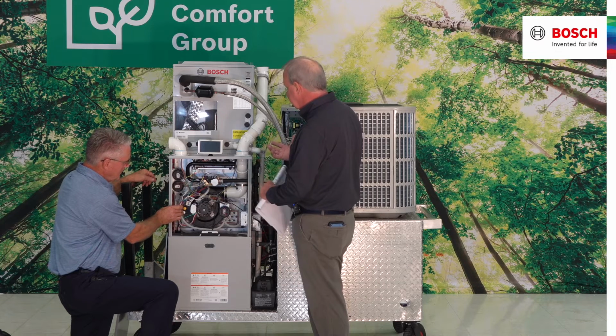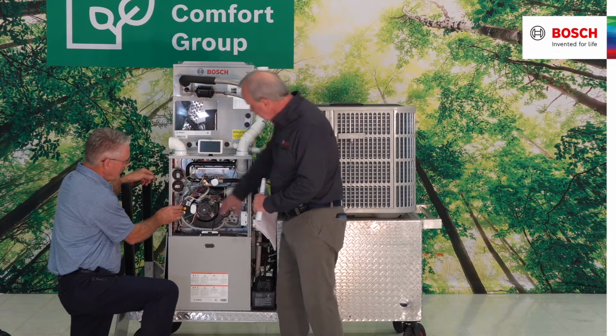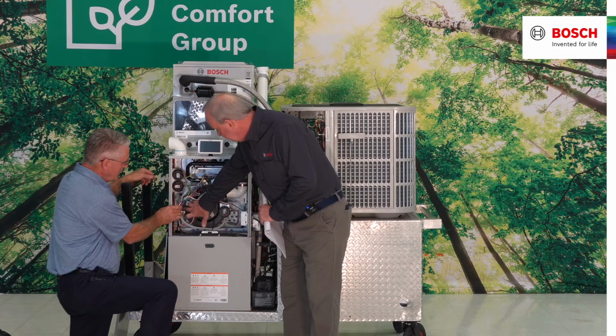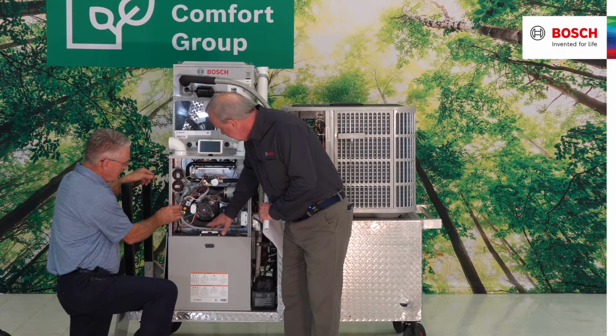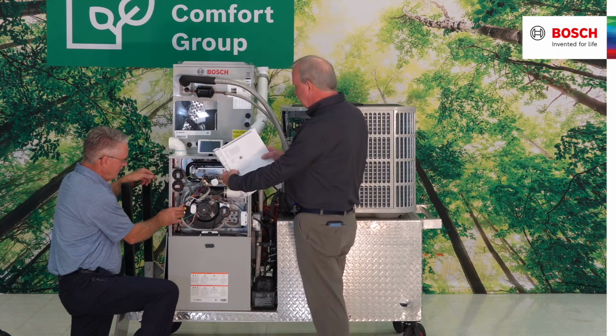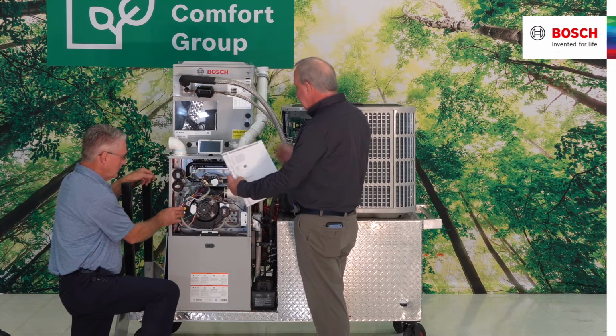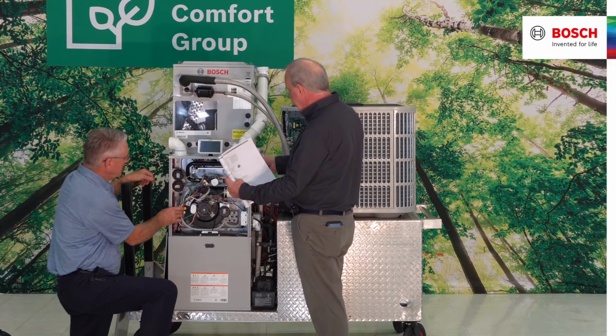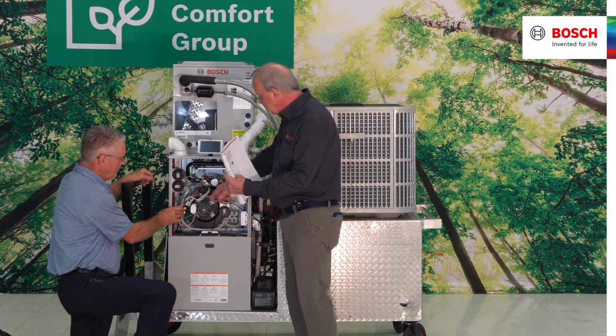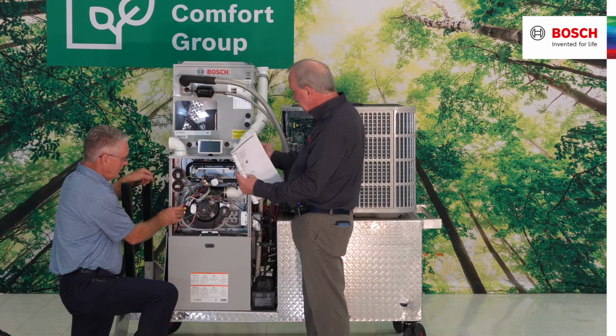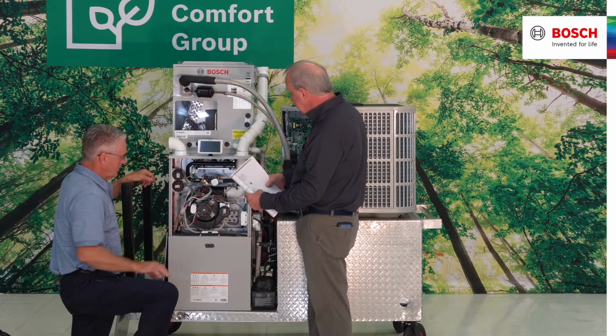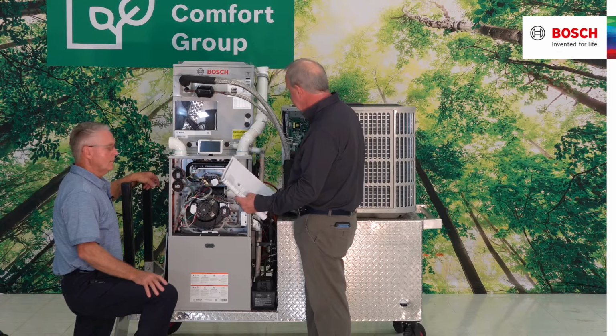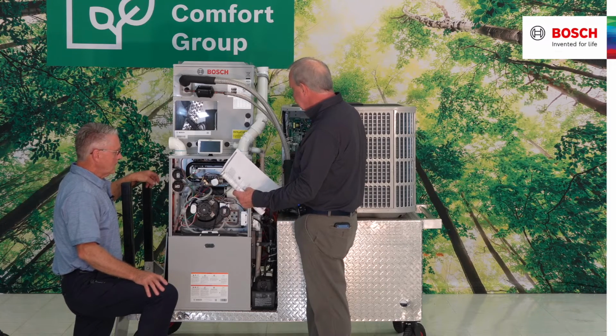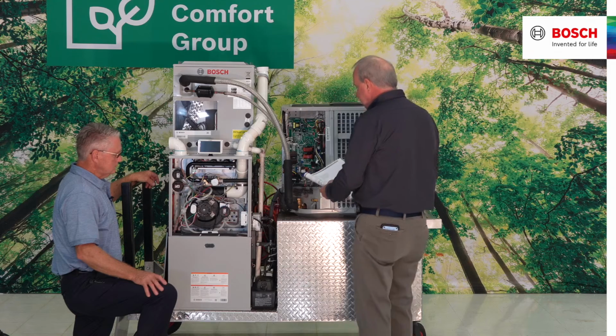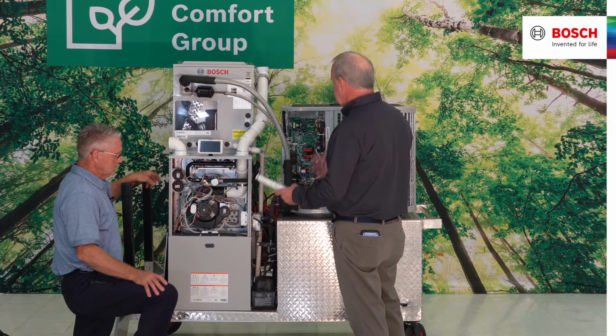Once again, this is a condensing furnace, so we're always going to have water coming out of it in the heat mode. There's a yellow plug over here on your induced draft motor housing, and you'll notice in the installation manual that when you're going left or right, you need to disconnect the existing drain and reconnect it, and then remember to take the cap off of the new location and put it back on the old location. Just pay attention to those changes when you're going to lay it horizontal left or horizontal right.